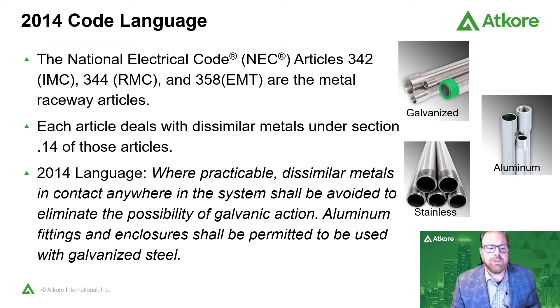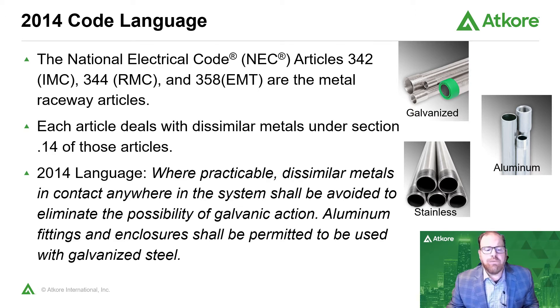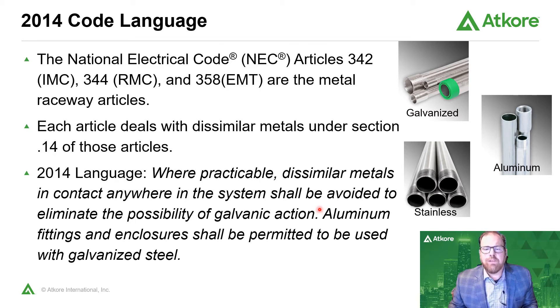The 2014 code language states: where practicable, dissimilar metals in contact anywhere in the system shall be avoided to eliminate the possibility of galvanic action. Aluminum fittings and enclosures shall be permitted to be used with galvanized steel. Looking at the pictures, we have galvanized conduit, aluminum conduit, and stainless steel conduit. In the 2014 code language, aluminum and galvanized are mentioned, but there is nothing about stainless steel. So in 2014 the code offers no guidance on what can be done to make the transition to stainless steel conduit.